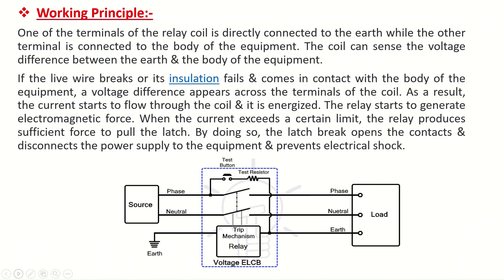Working principle of Voltage ELCB. One terminal of the relay coil is directly connected to the earth while the other terminal is connected to the body of the equipment. The coil senses the voltage difference between the earth and the body of the equipment. If the live wire breaks or its insulation fails and contacts the equipment body, a voltage difference appears across the coil terminals. As a result, current flows through the coil and it is energized, generating electromagnetic force. When the current exceeds a certain limit, the relay produces sufficient force to pull the latch, opening the contacts and disconnecting the power supply, thereby preventing electrical shock.